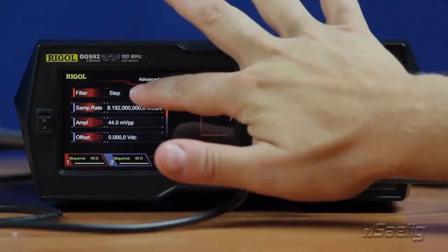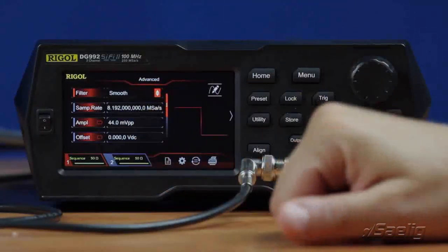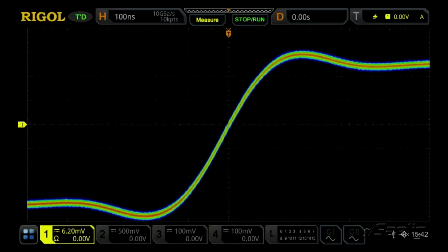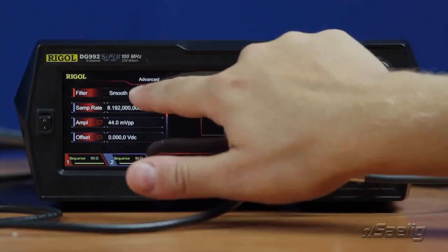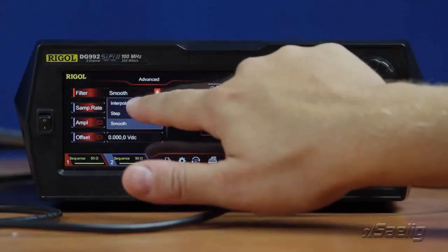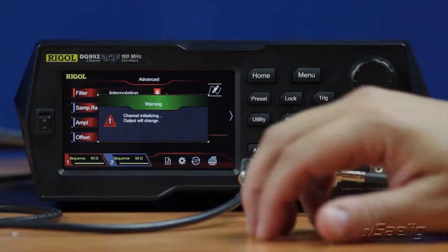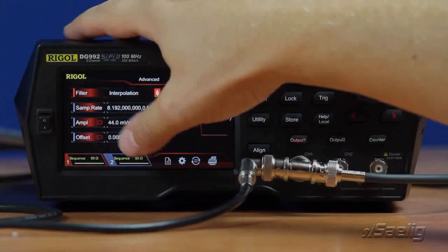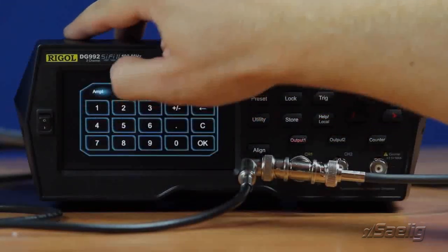We can take that same square wave and use the smooth filtering function. That gives you a little more overshoot, a little more higher frequency components, a little different look to the overall waveform. For complete customization, we can also use the interpolation mode.